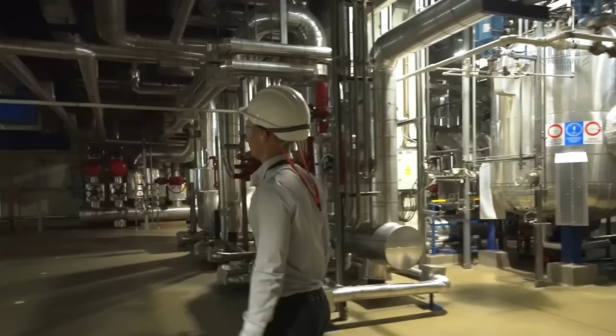Transformer explosions happen. They happen because of manufacturing defects, deferred maintenance, overloading, lightning strikes, and because aging mineral oil breaks down over decades, producing dissolved gases that lower the flashpoint of the entire system. In a network as old and underfunded as Bucharest's, a spontaneous failure would be entirely unsurprising.